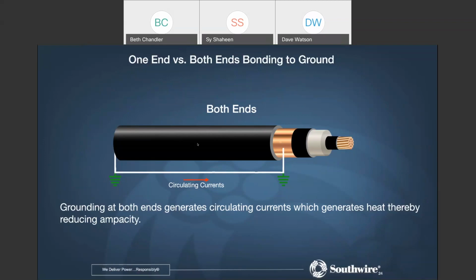But I want to make this clear: when you go by the NEC, the National Electric Code, they're assuming this. They're taking the worst case scenario. So the ampacities that you get from our tables or from the NEC are looking at this as the worst case scenario. In other words, it's looking at circulating currents as well. So that really is the difference. The other one, you get more ampacity. So if you really want to get more ampacity out of it, you might want to open up the shields. But if ampacity is not an issue, it's oversized, then you can ground them at both ends.